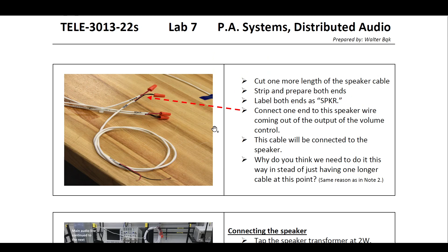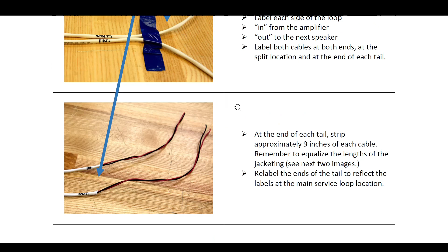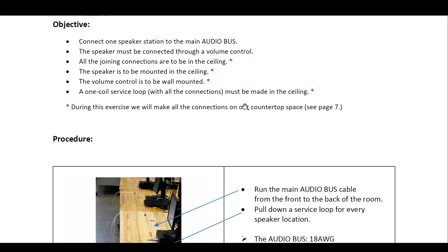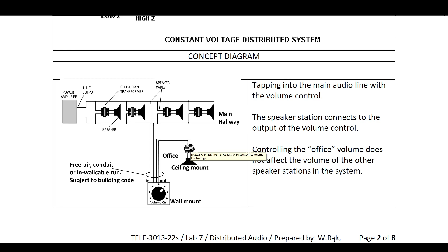All right, let's go back to where we stopped. That loop is going to be interrupted and joined right back together for the purpose of adding one more wire, and that wire is going to go into the volume control. We're cutting that loop, joining it back together, and adding a third wire which goes through the conduit into the input of the volume control. Then from the output of the volume control it goes back, ending up in the same service loop, but connected only to the primary side of the transformer.